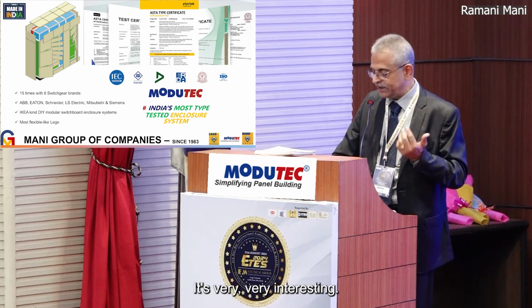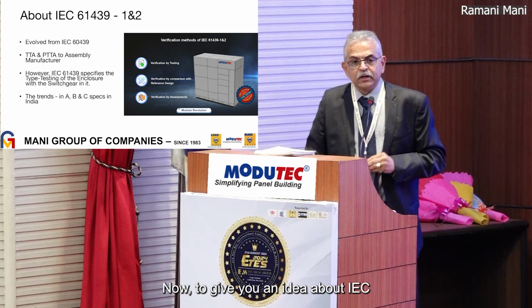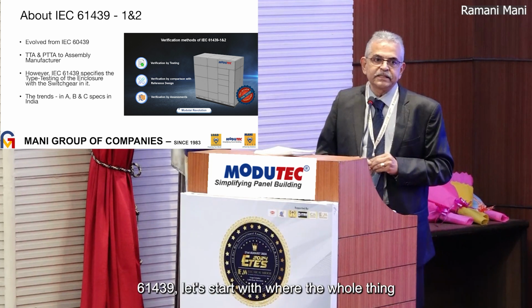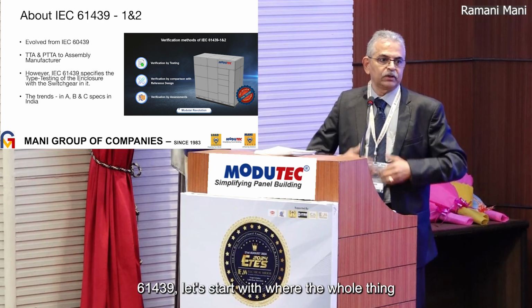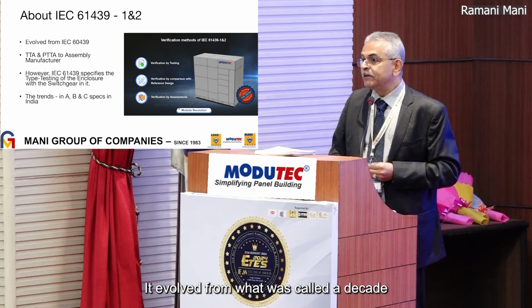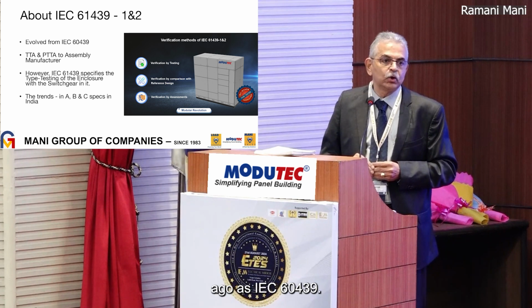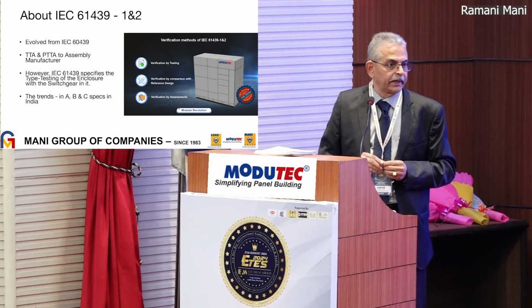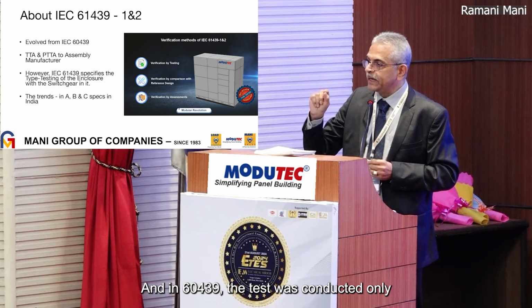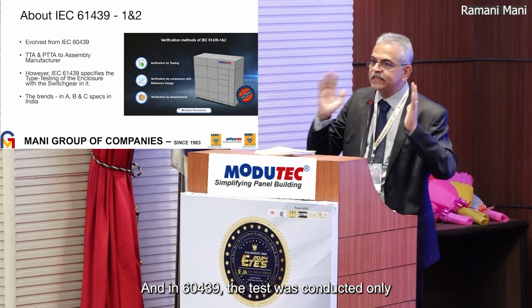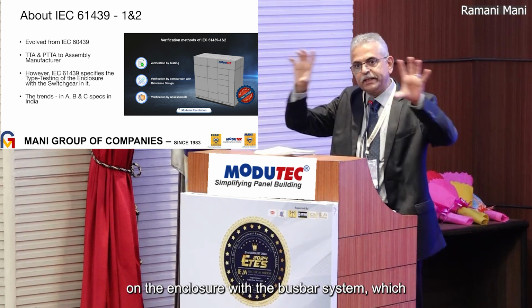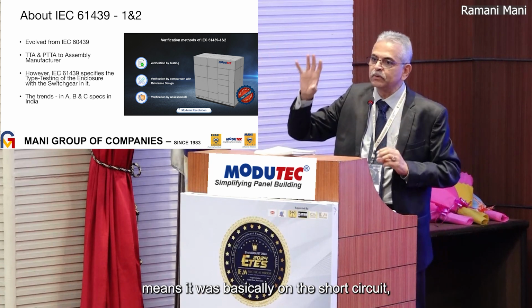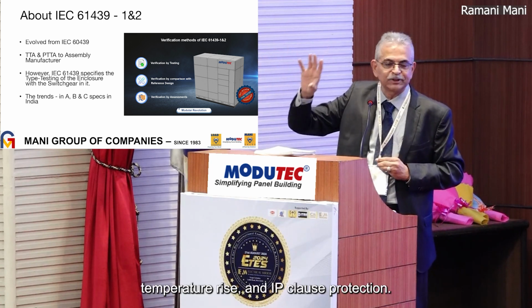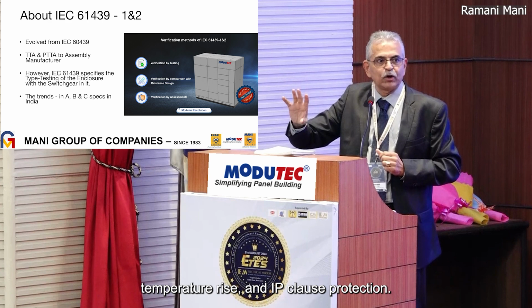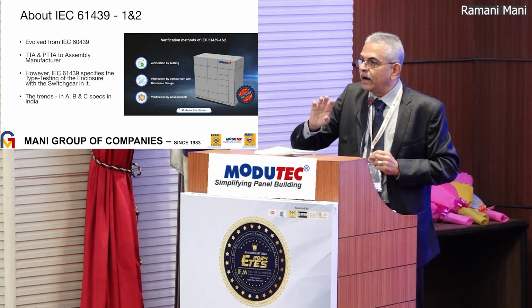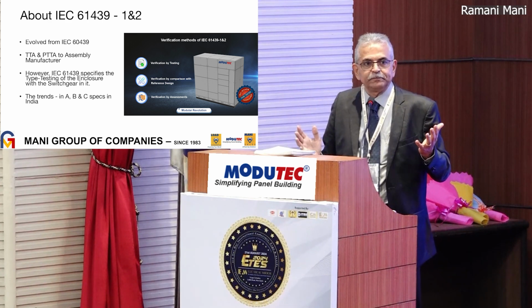Now, to give you an idea about IEC 61439, let's start with where the whole thing evolved from. It evolved from what was called a decade ago as IEC 60439. And in 60439, the test was conducted only on the enclosure with the busbar system, which means it was basically on the short circuit, temperature rise, and IP clause protection. It did not have anything to do with the switchgear.